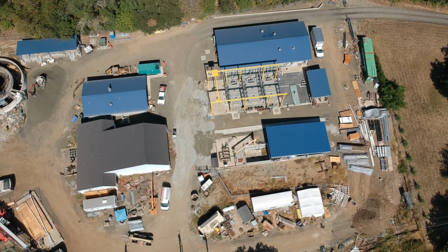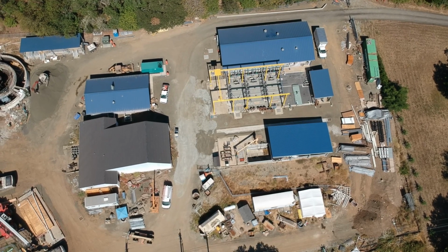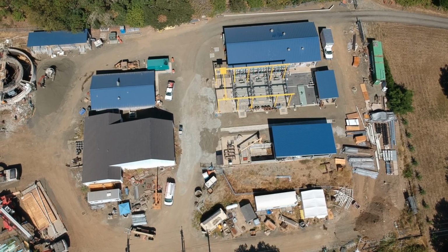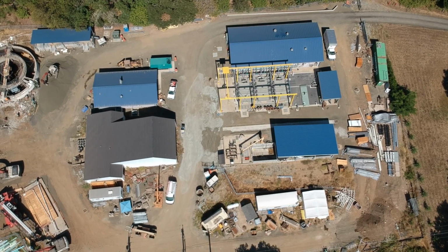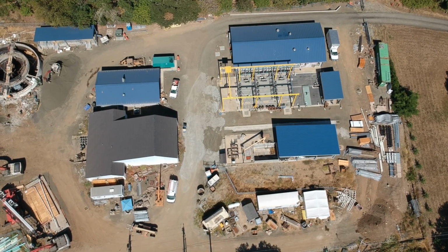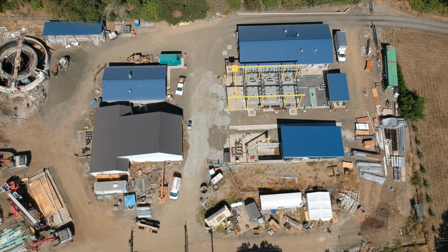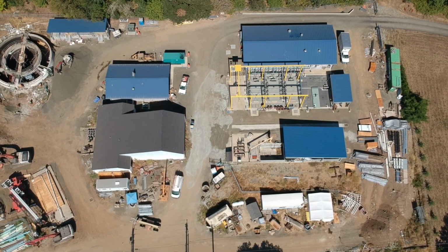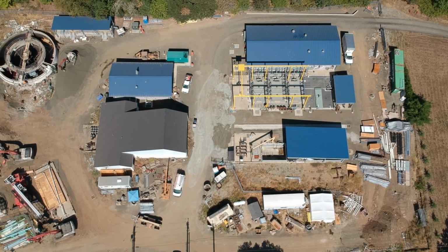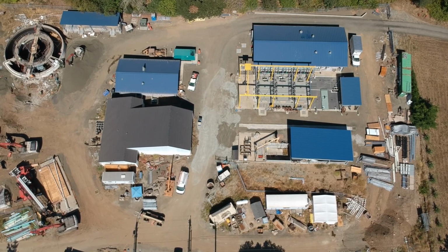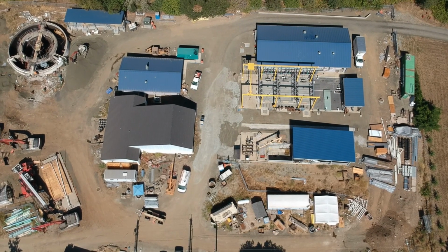There is no forced aeration in this anoxic tank. Heterotrophic bacteria populate the environment. Biological denitrification occurs in this tank, where nitrate is converted to nitrogen gas and expelled to the atmosphere. With the denitrification process, we also recover about 50% of the alkalinity lost during the nitrification process.